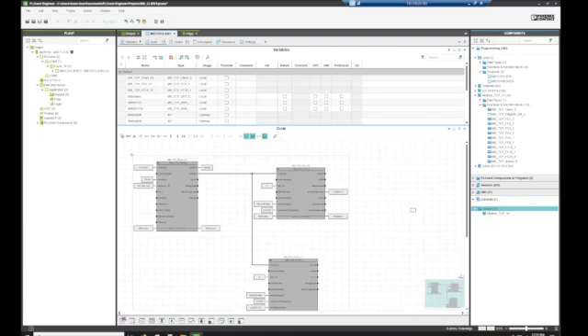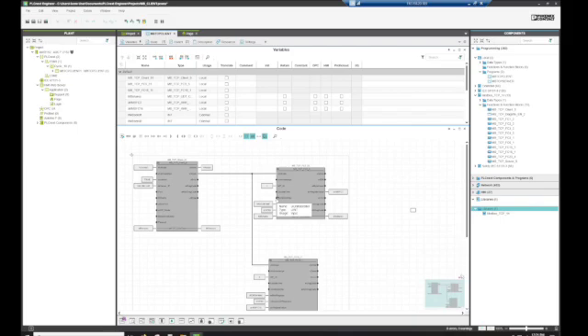Update time, that's how quickly do you want the block to cycle. They can be different, and I believe the default is 500 milliseconds, which is fine for today. The unit identifier, that would be if you had a Modbus RTU device being pushed over TCP through like a gateway. You may need to find that device as a separate piece.